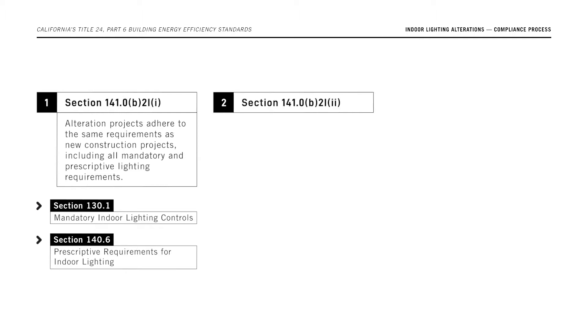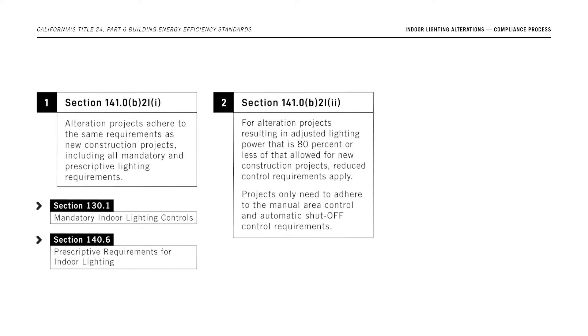Option 2: For alteration projects resulting in adjusted lighting power that is 80% or less of that allowed for new construction projects, reduced control requirements apply. Projects only need to adhere to the manual area control and automatic shutoff control requirements.